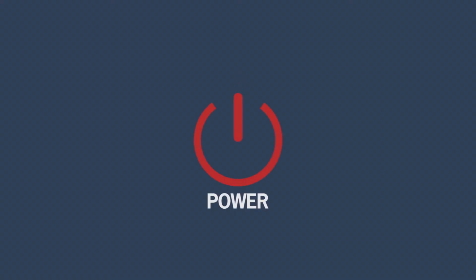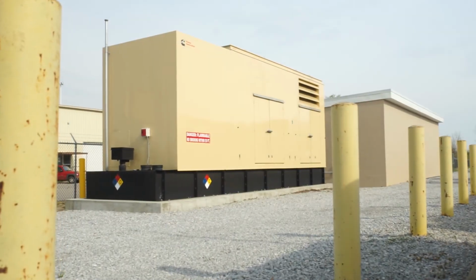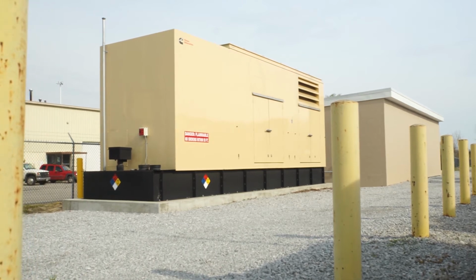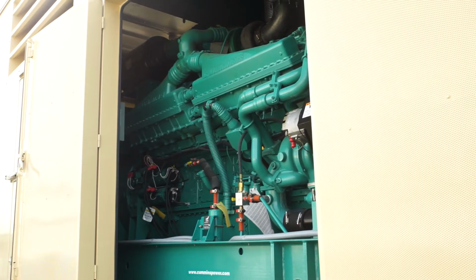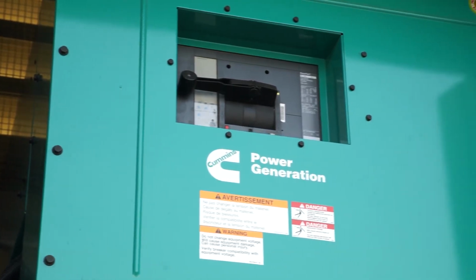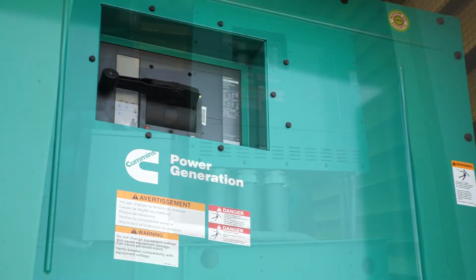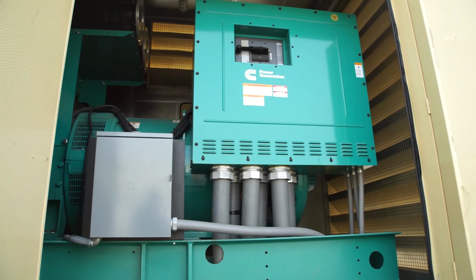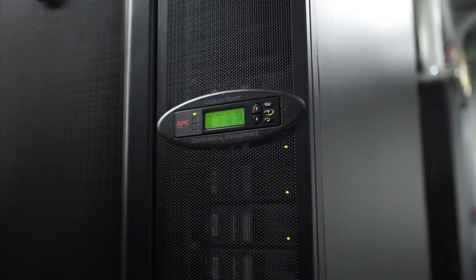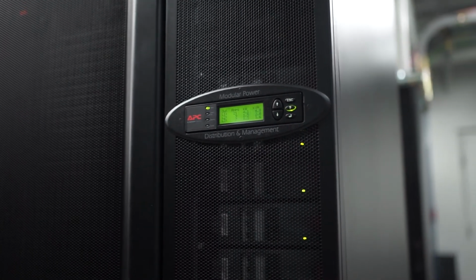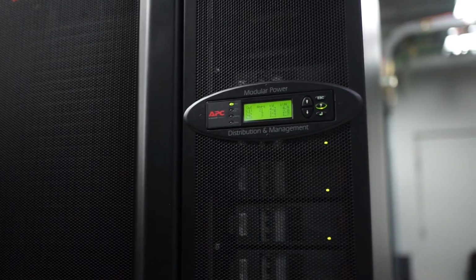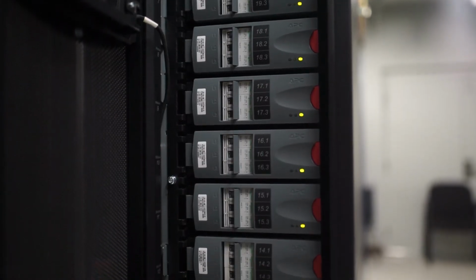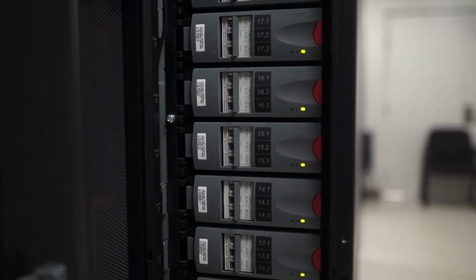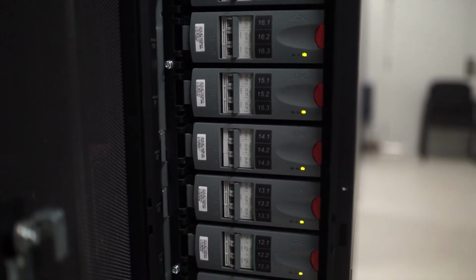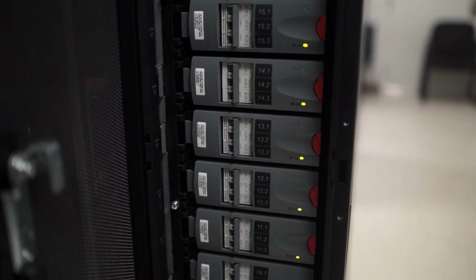With Data Center 1, we've taken every precaution to protect our customers' data and the ability to access it. With DC-1, we have redundant 1.6 megawatt generators. In the unlikely event that one generator fails, our secondary generator will immediately activate to provide constant power. In addition to our generators, by default, each cabinet comes equipped with dual uninterruptible power supplies, or UPS. This is an additional measure to ensure your equipment is always powered, along with saving the expense and space of providing your own power backup solution.